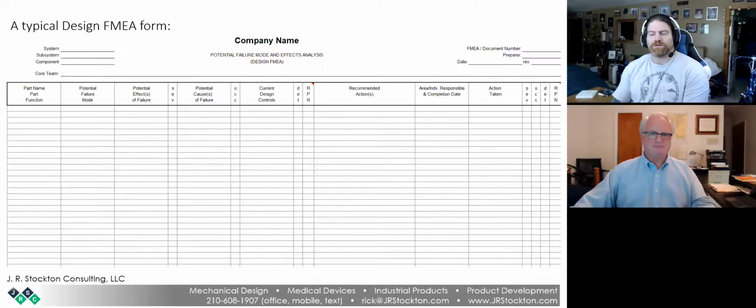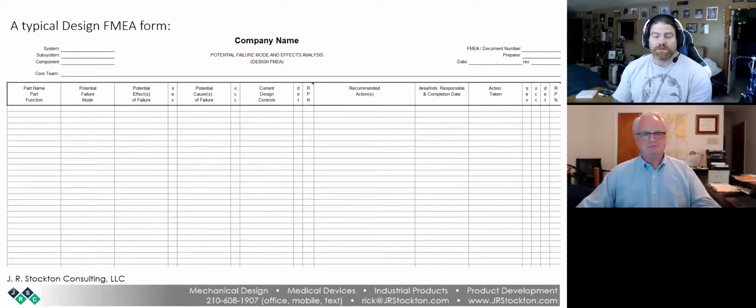And this is what is acceptable for risks in those products, and we shouldn't make a product that's worse. That should be one way you look at acceptability of risk: do the state of the art review, determine what acceptable risk is based on state of the art, and then make your product as safe or safer.